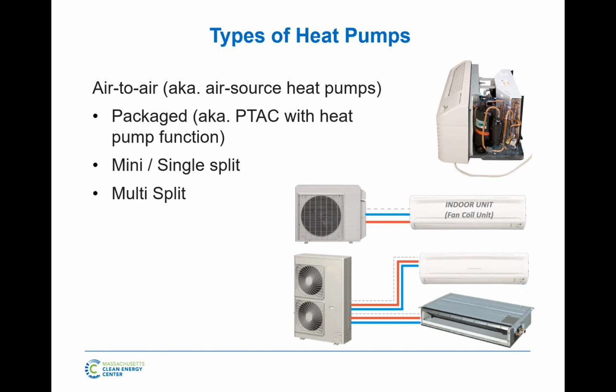And then we get into our favorite, at least Greg's and mine, and a lot of people in the room, which is the air-to-air heat pumps. In theory, there are some PTACs, which are through-the-wall units in hotels, that are air-to-air, because they take heat from the room in the summer and throw it outside. But some of them come with heat pump functions, taking heat from the outside and throwing it inside. But the technology in here, the size of the condenser coil, doesn't allow these to work down to very, very cold temperatures, so usually they have electric heat in them or even gas heat as well. But that's an air-to-air heat pump, or it can be.